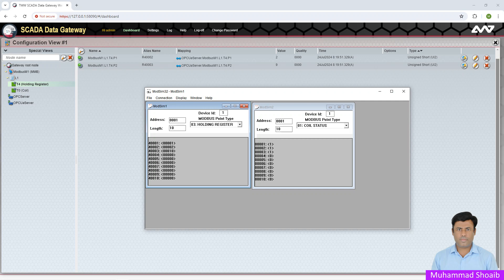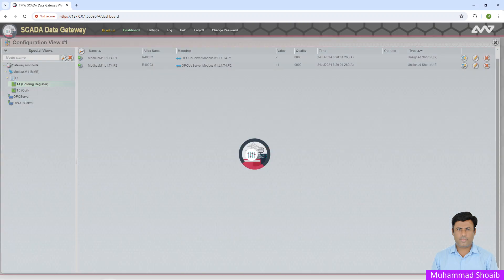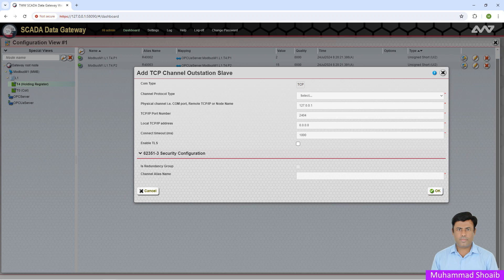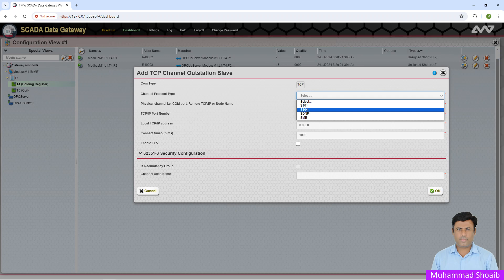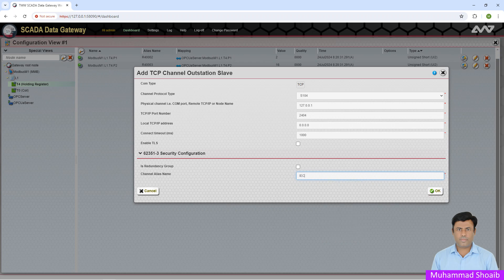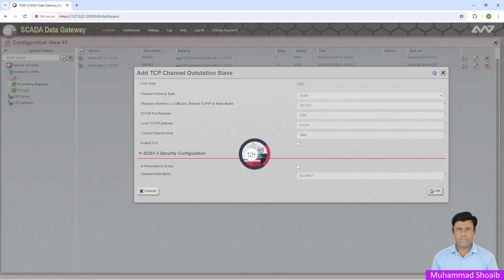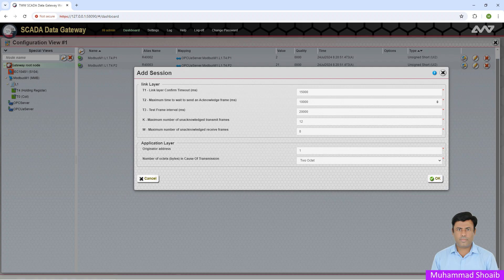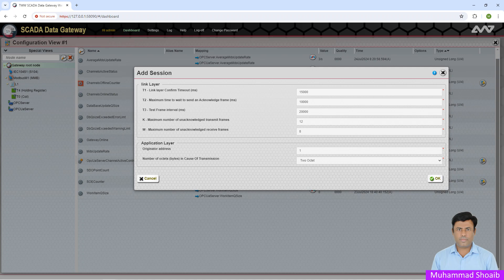Now we'll move to the second step — configure IEC 104 as a server. Come to the gateway root node, right-click, and select TCP Channel Outstation Slave Device. Select the protocol — for our case it will work as IEC 104 server. You can name it 'IEC 104 Server 1'. Press OK. Keep the other settings as default and press OK.